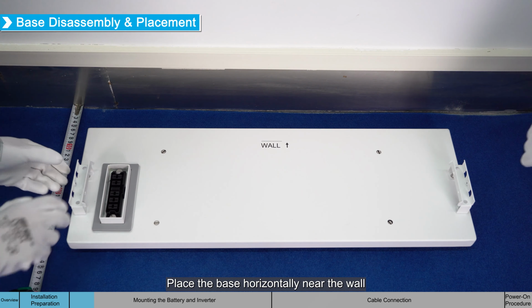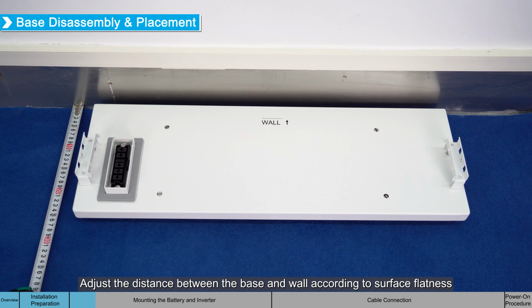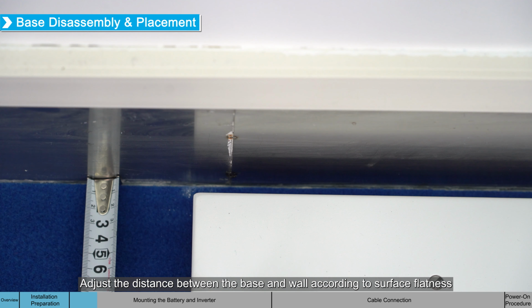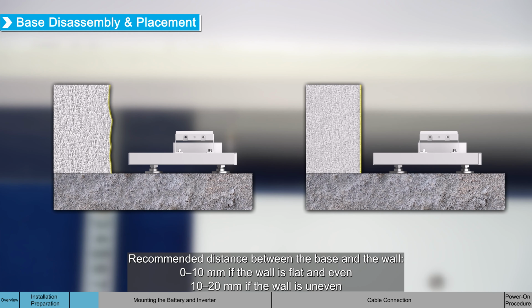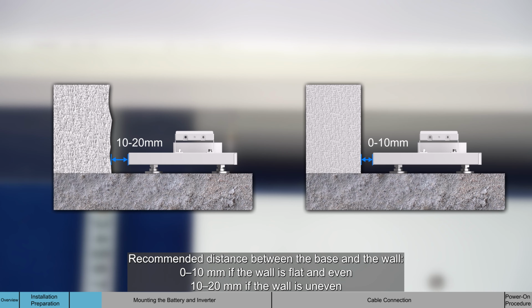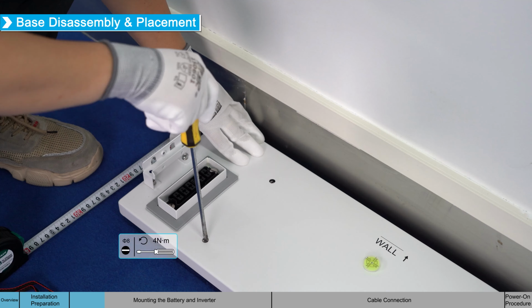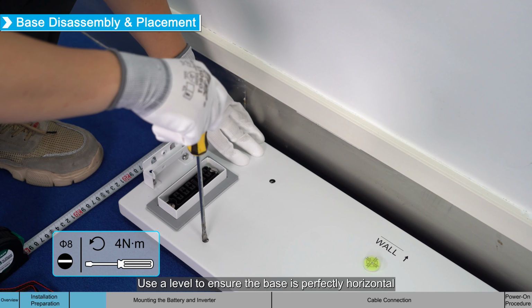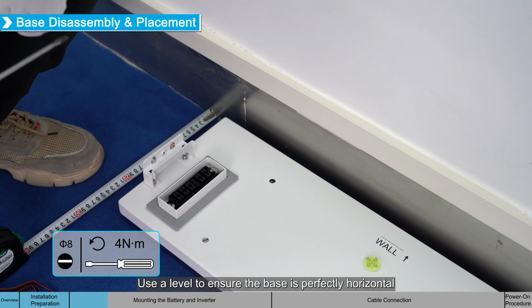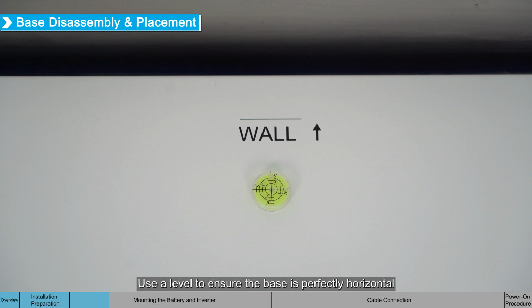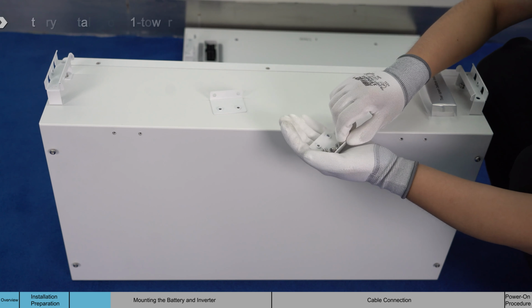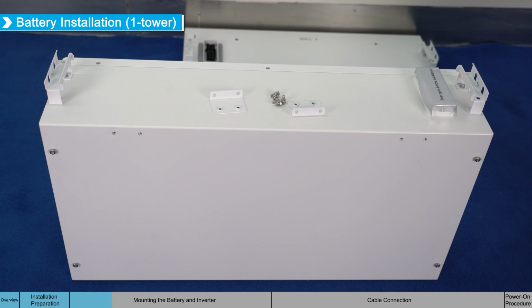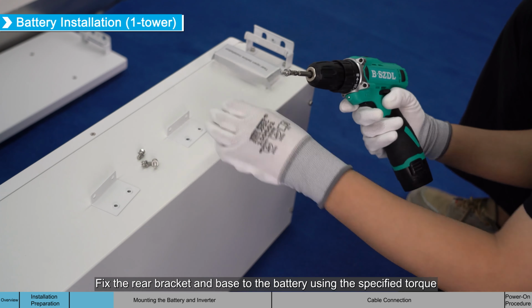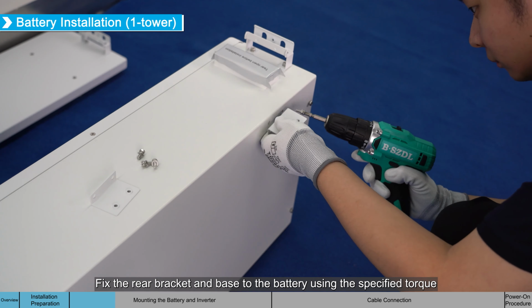Place the base horizontally near the wall. Adjust the distance between the base and wall according to surface flatness. Recommended distance between the base and the wall, 0-10 mm if the wall is flat, and 10-20 mm if the wall is uneven. Use a level to ensure the base is perfectly horizontal. Fix the rear bracket and base to the battery using the specified torque.